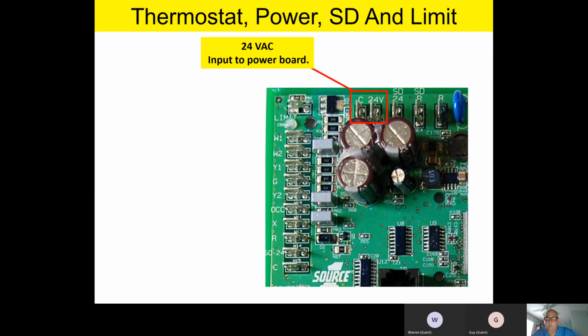As we move up towards the top of the board, this is where we bring power into the board. There's that C and 24V. That's what powers up the board. Now remember, guys, this is where your transformer is actually going to be hooking up, between C and 24V. And it powers the microprocessor all the time. Even if the unit is shut down by the SD24 and SDR circuit, if that circuit's open and the unit is non-operational, you're still going to have power to power up its brain.